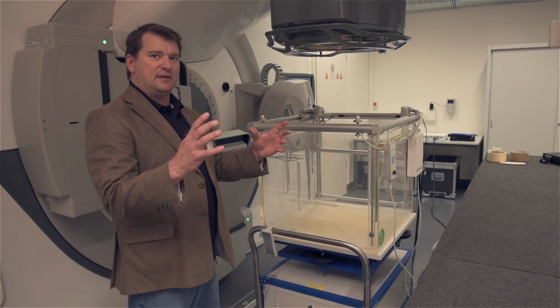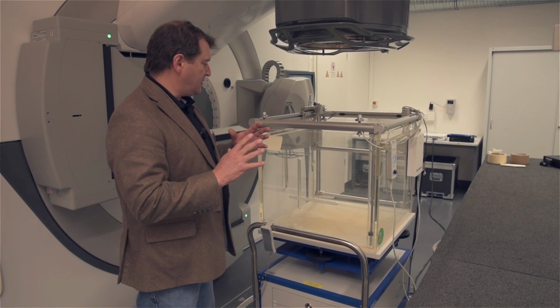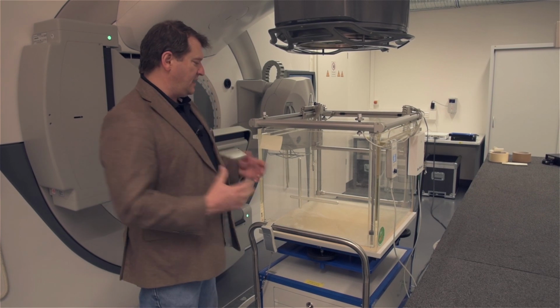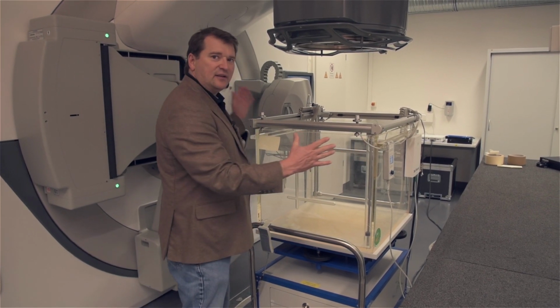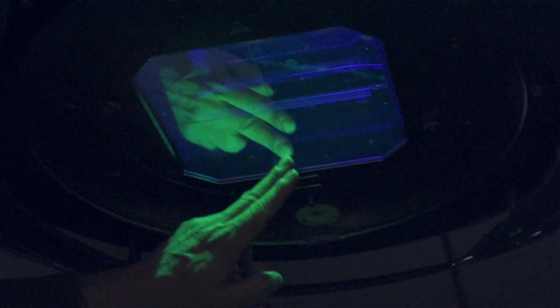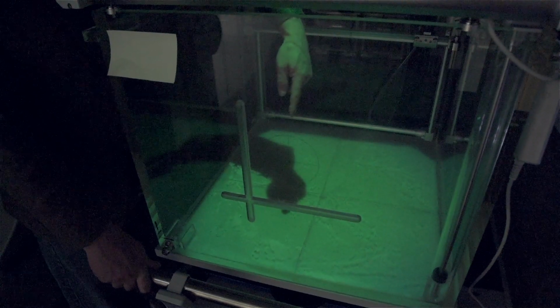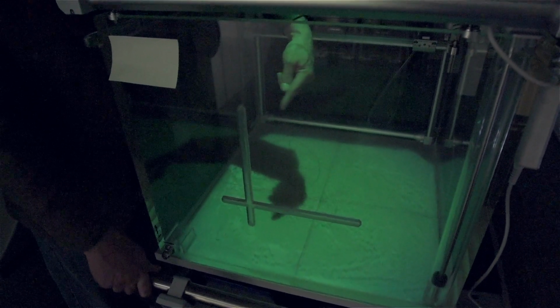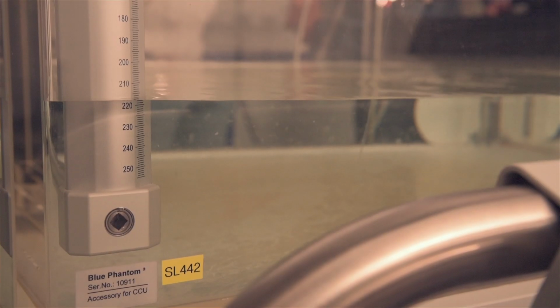For final alignment, while the tank's still empty of water, I'll turn the lights back off and then just physically shift the tank until I get it exactly where I want it. So there are the crosshairs that are projected by the light of the accelerator head onto the bottom of the scanning tank. We're looking for the shadow of the crosshair to fall directly on top of the etched crosshair. Once you're there, you're ready to put water in.